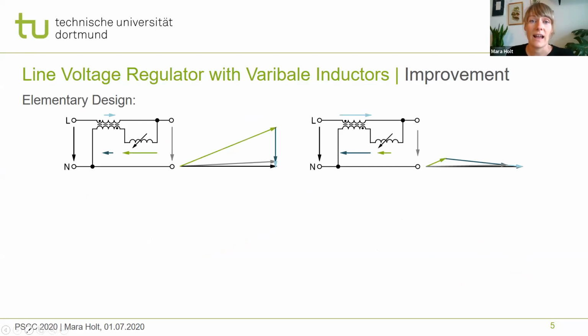The elementary design has a main disadvantage. If the variable inductor has a high inductance in the initial state, the transformer is almost in no-load operation. As a result, the magnetizing reactance of the series transformer has a high inductive impact on the grid impedance. And as you know, an increased grid impedance causes unwanted effects, such as a reduction of short circuit current and reduced interference immunity to power quality.